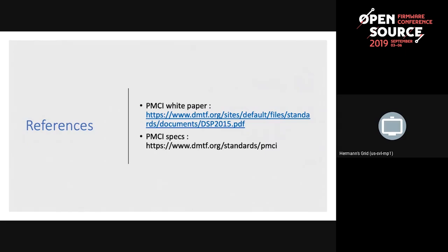There are problems with IPMI: the sensor limit was one I spoke about, and IPMI also lacks control mechanisms. So PLDM effectors is an effective way for controlling states, for example. And even with the transport interfaces — IPMI spec defines block transfer as one of them — there are benefits you would see comparing block transfer versus MCTP: MCTP abstracts you from physical mediums and there are more physical mediums supported in general compared to IPMI.